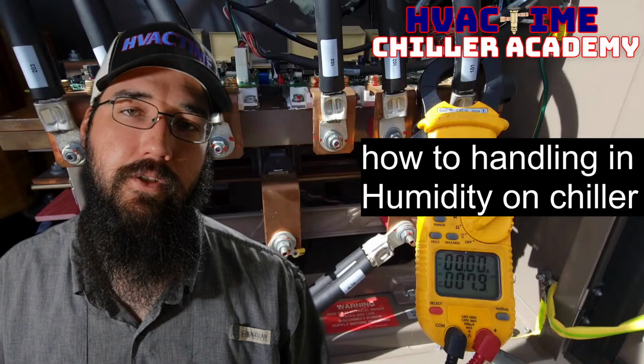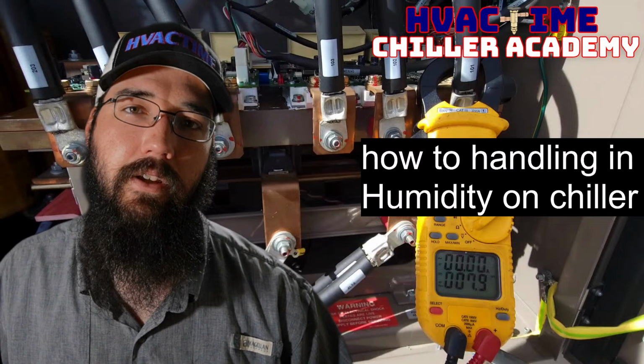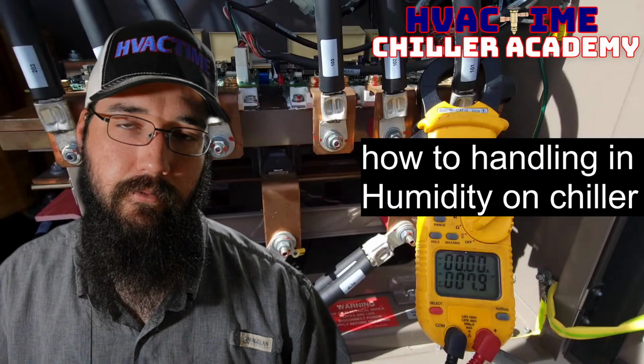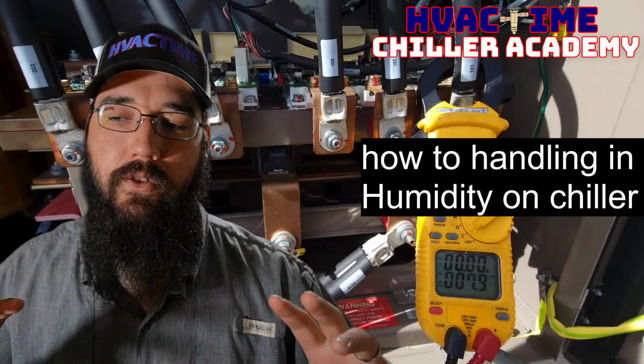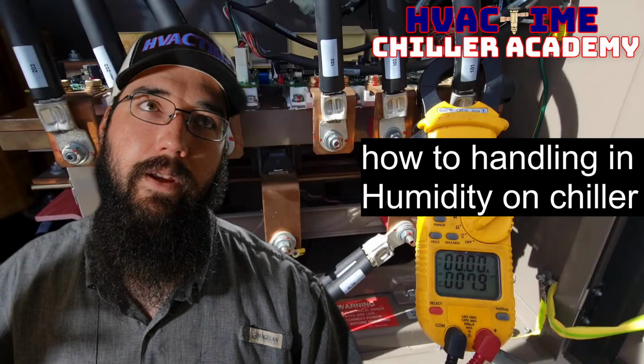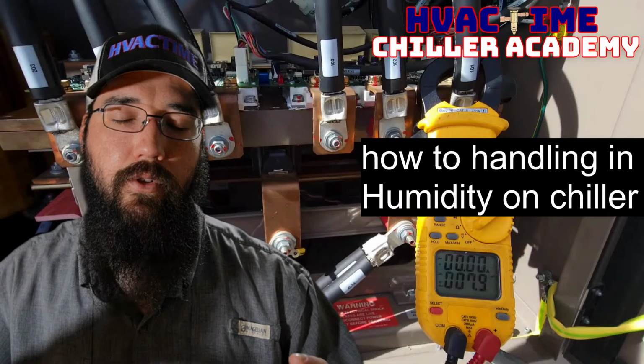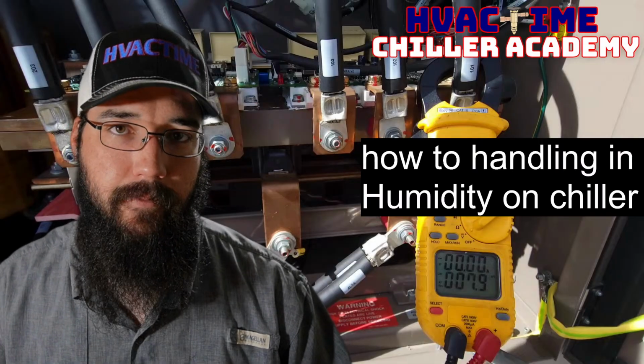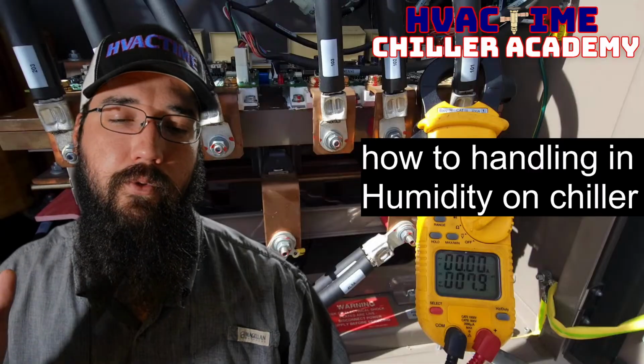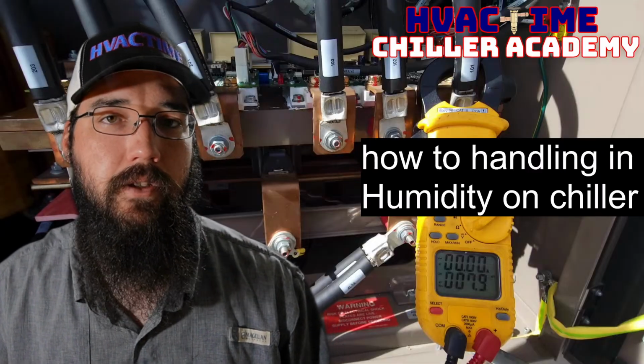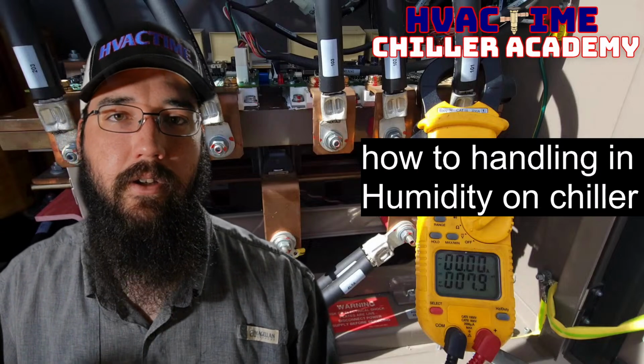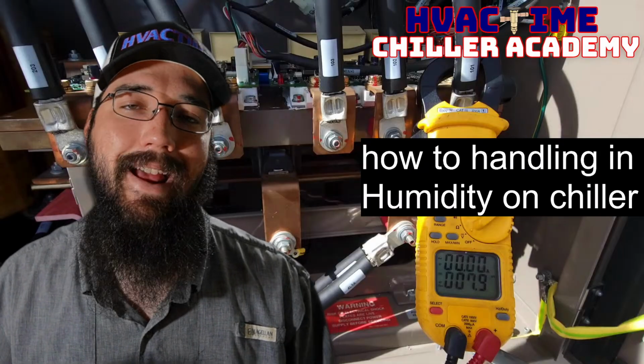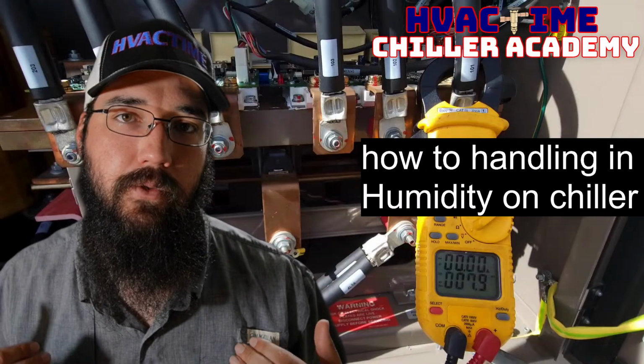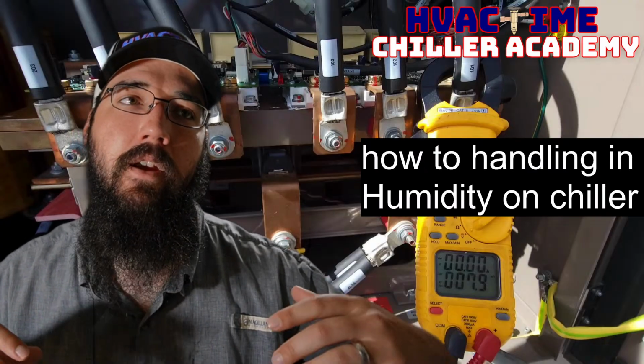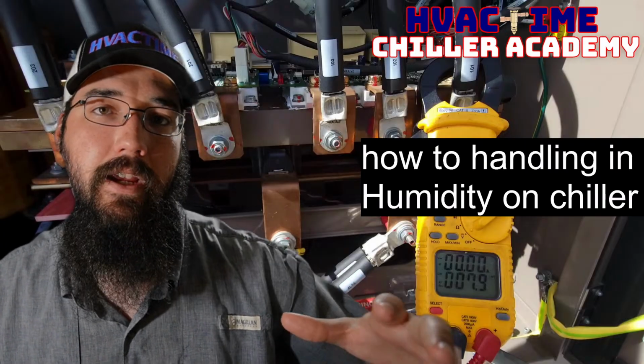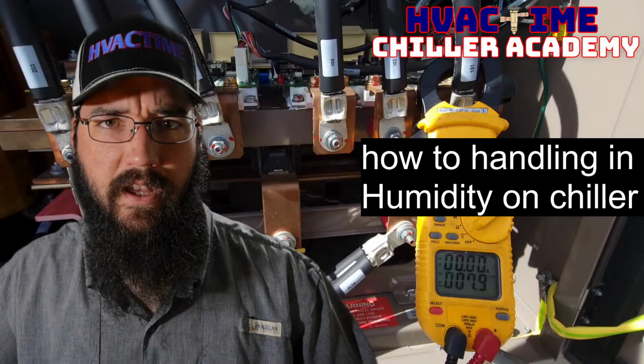And this is slightly different with chill water, because lowering airflow, lowering the CFM, doesn't lower your saturated coil temperature, which in our case, 45 degrees set point. So those don't track the same way. And what we end up having to do is, you can just lower that set point a little bit at the chiller. So 45 is your standard. Go to 43 or 42. You know, don't get too crazy with the adjustments. It's not going to take a whole lot. A little bit of an adjustment, a couple of degrees at a time, will make a huge difference in how much more latent heat that coil is able to take in. And the colder we can get that coil, the more we can transition the ratio to where we're taking in more latent and less sensible to help with that dehumidification process.